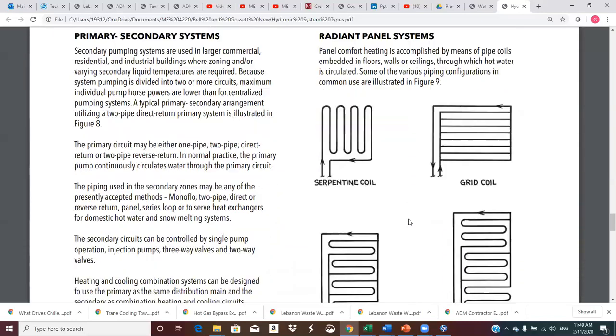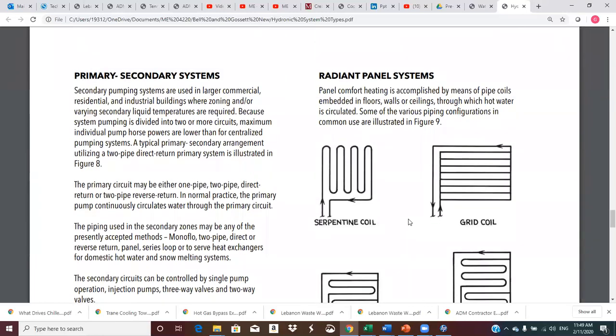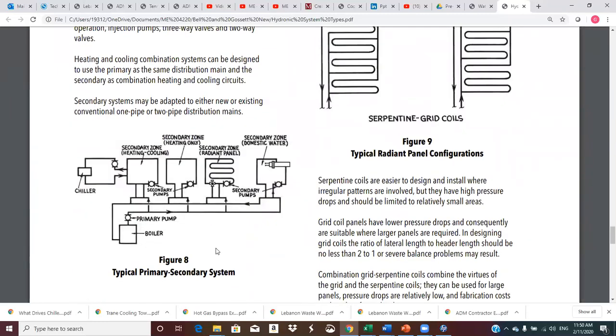Okay, we have primary-secondary systems, and we'll spend a bunch of time going through this, so I'm not going to stress it too much right now. You should read through here, but basically, on the boiler, we have a central distribution loop that is carrying hot water. This would be the primary. It's coming out here, going down and coming back. Then we have secondaries, which could be a whole building or a separate room. When the secondary pump runs, it pulls water out of this primary loop and pumps it through this secondary for heating and then returns it back to the boiler.